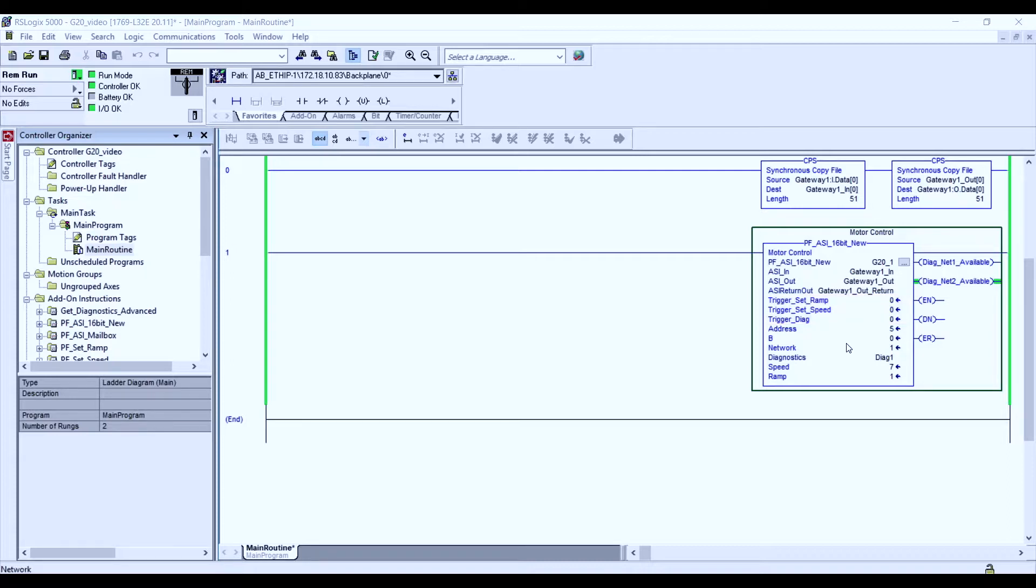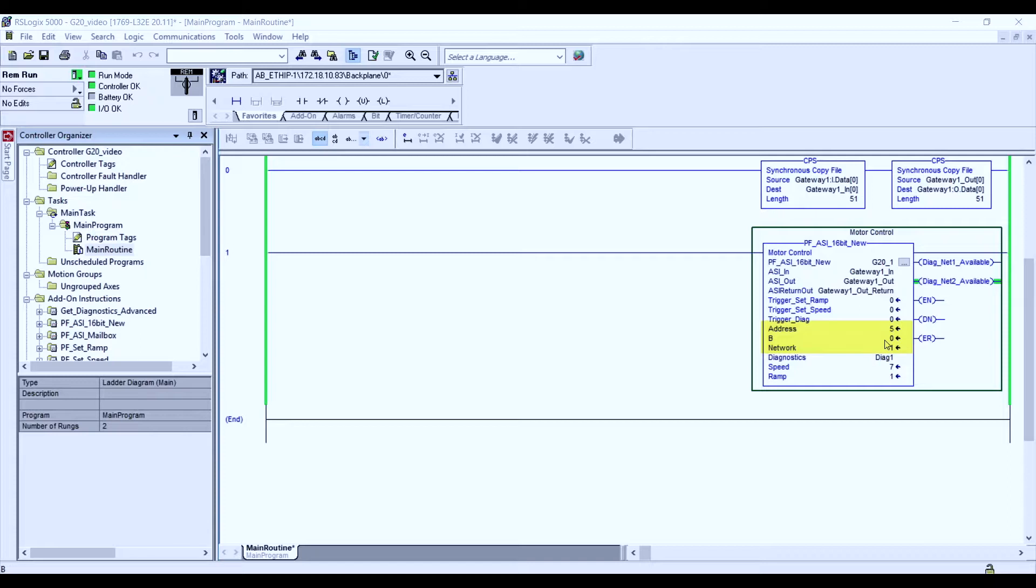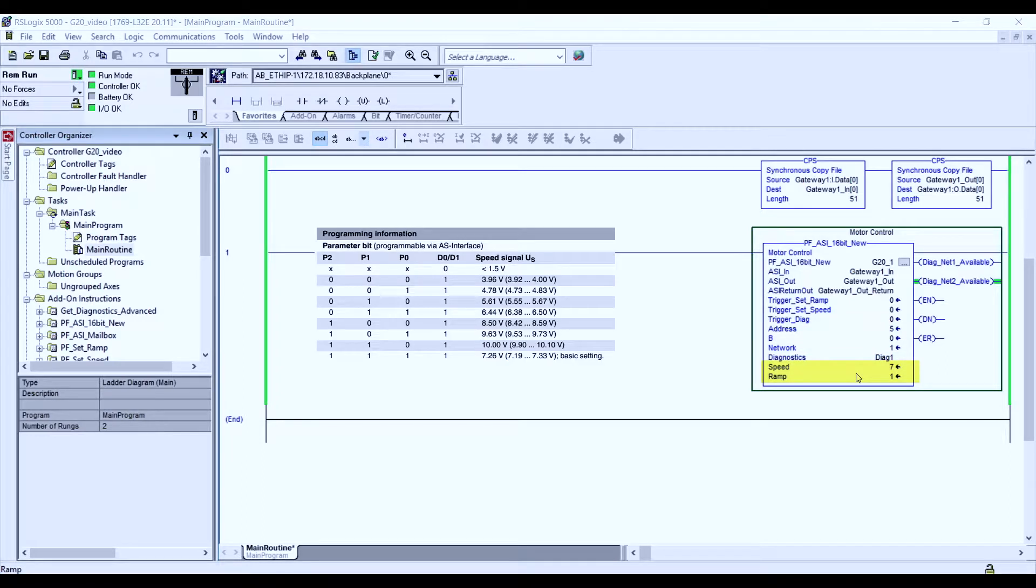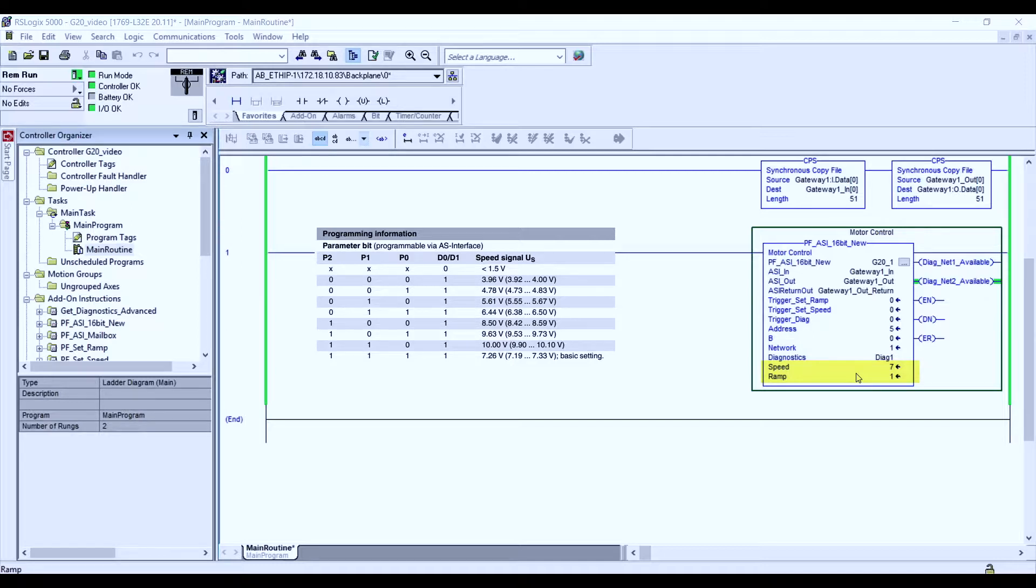Currently, we have to make sure in the add-on instruction which motorized drive roller module we want to affect. In this case, we're using our 5A node address. The B indicates if you have a B address or an A address. In our case, we are using an A address. The network signifies if we are on network 1 or 2. The speed and the ramp parameters associate to the parameter bits. These bits have values from 0 to 7.